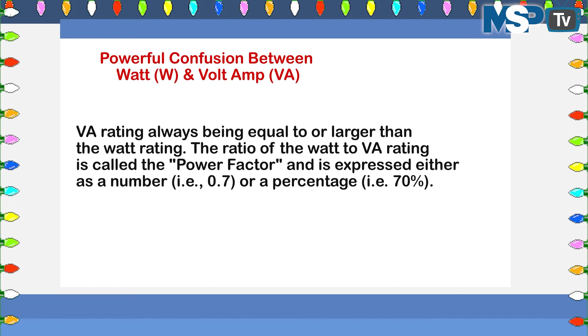The power ratings of the UPS. UPS have both a maximum watt rating and a maximum VA rating. Neither the watt nor the VA rating of a UPS may be exceeded. It is a de facto standard in the industry that the watt rating is approximately 60% of the VA rating for small UPS systems, this being the typical power factor of common personal computer loads.